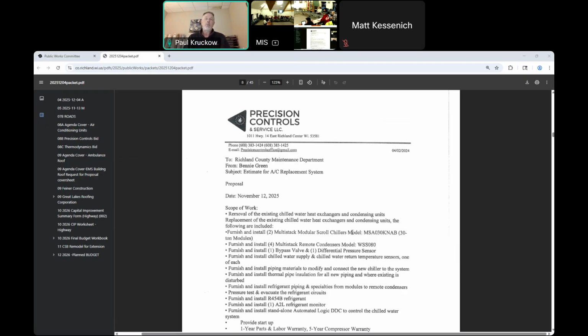So if circuit 1 sprung a leak, you still have circuits 2, 3, and 4, and so on. You don't have a true 60 tons of redundancy, but you have cooling available. You're not dead in the water if you lose a circuit or a module. And you don't necessarily use a full 50 tons of cooling all day long in the summer. You're probably functioning on half of that capacity most days or less, depending on the load, some days maybe more. As part of this whole package, there's no glycol involved and no additional pumps that we're adding.